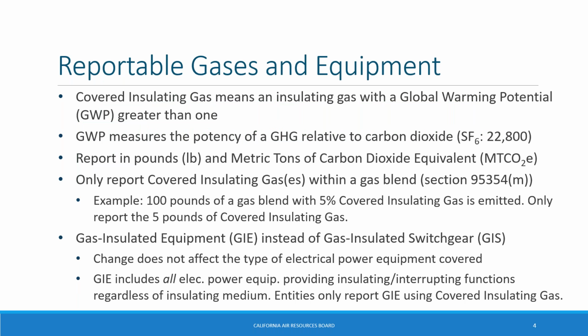This slide describes the gases and equipment types required to be reported under the regulation. In recognition of emerging technologies, the regulatory amendments broadened the scope of gases covered. The original regulation only required tracking and reporting of SF6, whereas the amended regulation applies to all covered insulating gases. Covered insulating gases are those with a GWP greater than 1. GWP is a metric that describes the potency of a greenhouse gas relative to carbon dioxide over an established time period. The GWP of carbon dioxide is 1, and the GWP of SF6 used in this regulation is 22,800.